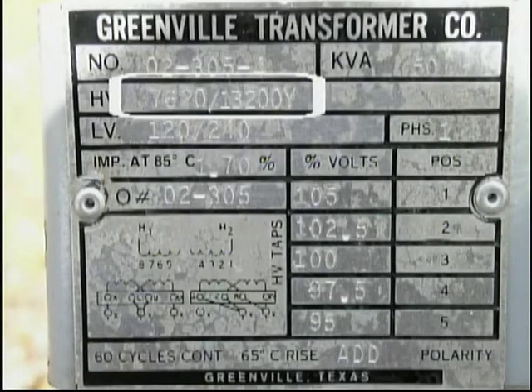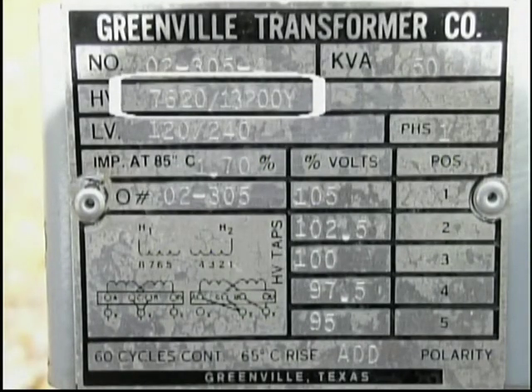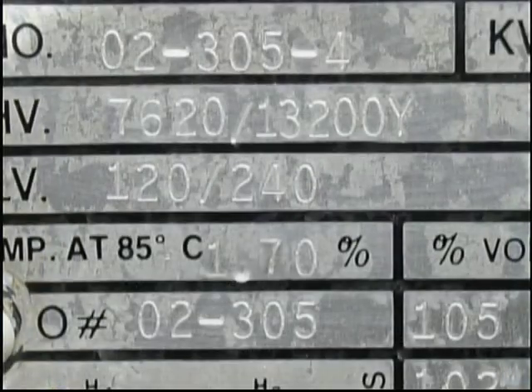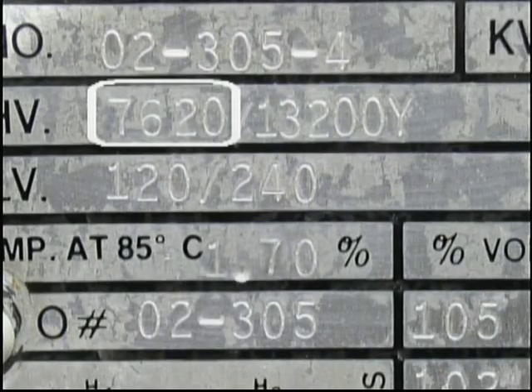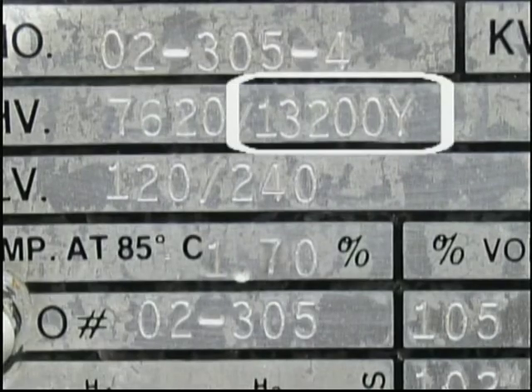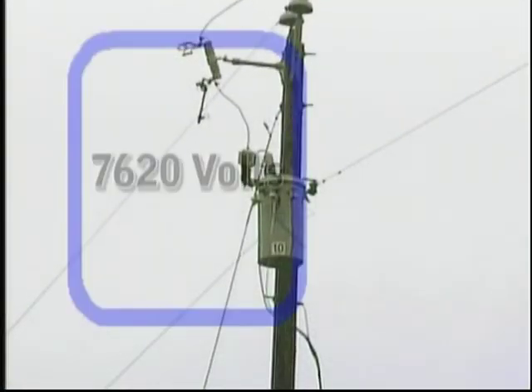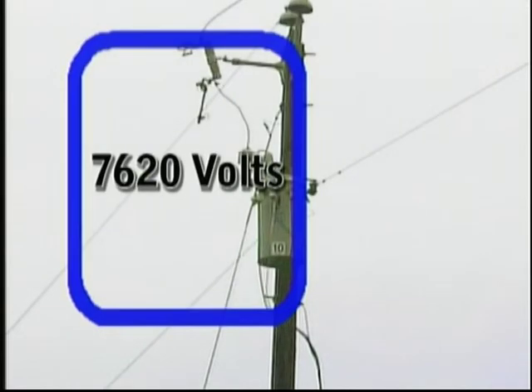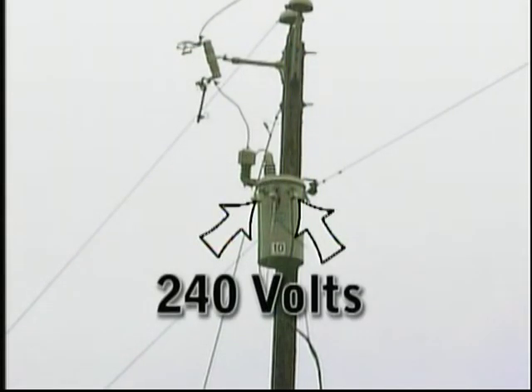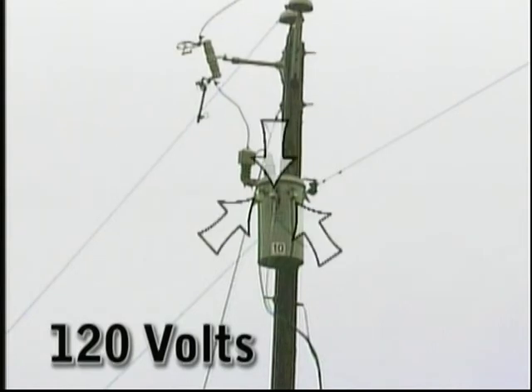On this unit, for example, the voltage rating is 7620/13200Y. As we said earlier, the first number indicates that the primary winding is rated and insulated to 7620 volts. The second number, 13200Y, indicates that the transformer is designed to be used on a 13.2 kV Y system. When all connections are made and the unit is energized, 7620 volts will be supplied to the primary winding. The voltage induced in the secondary winding will provide 240 volts to connections between the two hot legs and 120 volts to connections between either one of the hot legs and the grounded neutral.